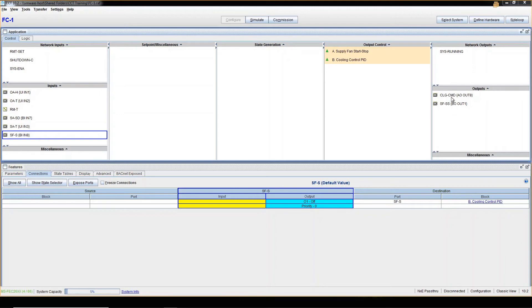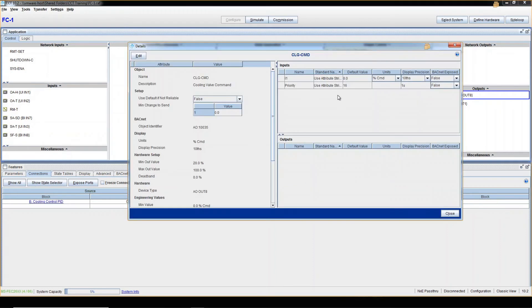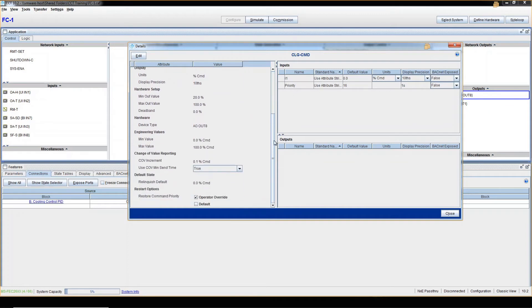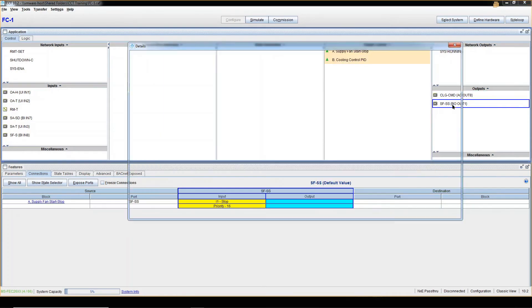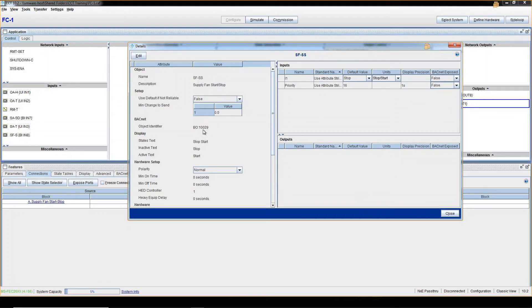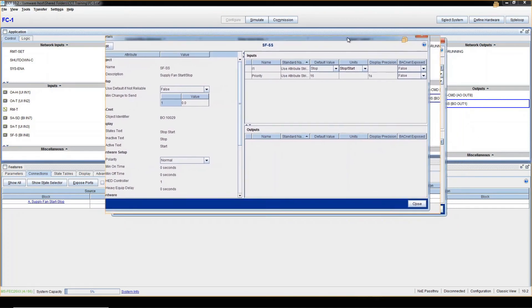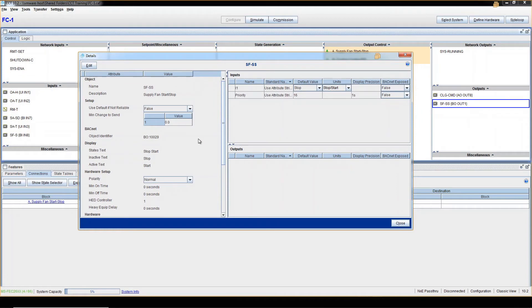Now physical outputs: the first one is Cooling Command and I can tell it's an Analog Output — analog means a number. The units are percent command, so it's a number from 0 to 100 — that's a Float. Supply Fan Start/Stop is a Binary Output, but again physical outputs aren't really Boolean — they're considered Enum, specifically two-state Enum: Stop/Start or Off/On.